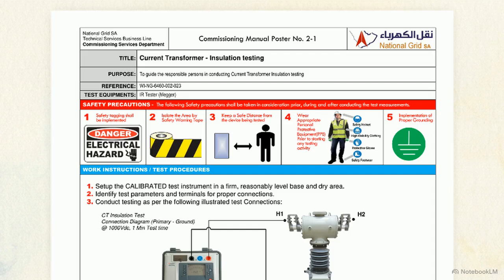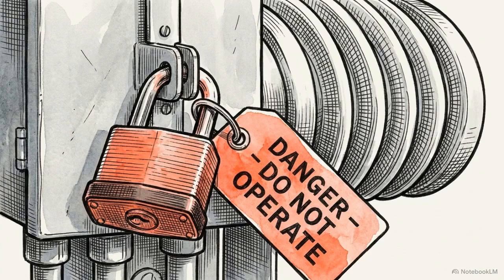Because of the open secondary hazard, testing never begins without isolation. The protocol requires 5 distinct safety steps: applying safety tags, isolating the area, maintaining safe distances, wearing appropriate PPE, and implementing proper protective earth bonds. Every procedural hold point and secondary shorting step in the commissioning matrix exists specifically to mitigate the physics of an open circuit voltage spike.